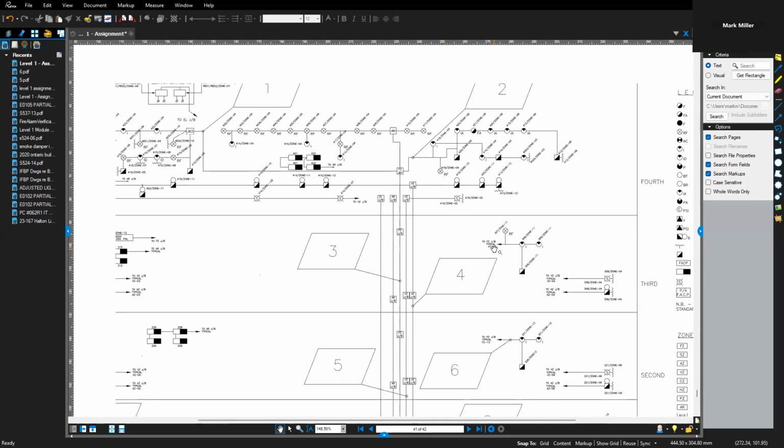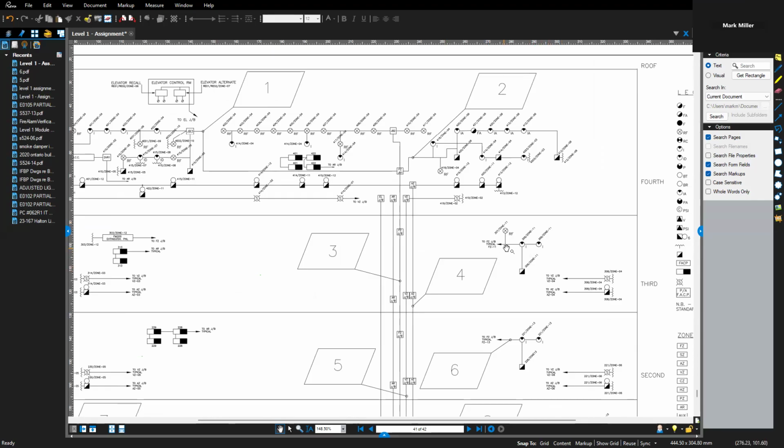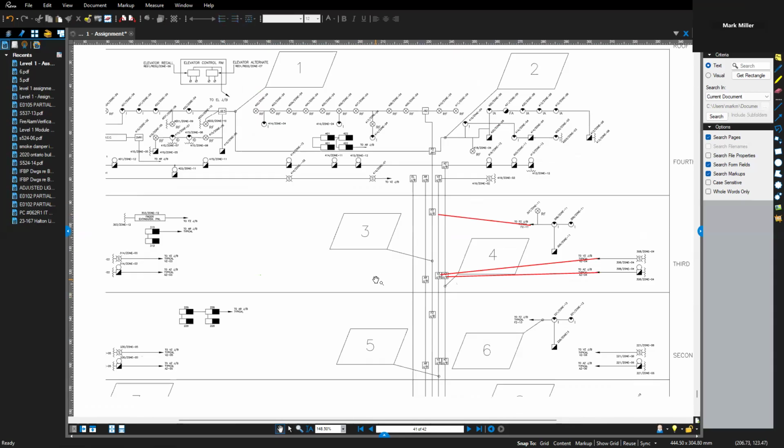We're seeing typical, right? We're seeing there's devices, it's typical, and it goes back to fire zone 11. So this pipe goes back to the junction box there. It's just not even shown in. This visual zone junction box, typical, and this one here. So we need to be aware of that. It's typical. We're not seeing everything. We only have parts of the drawing. So we have to be mindful of that.